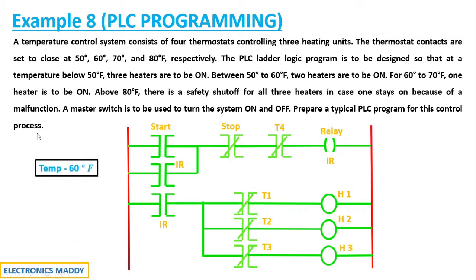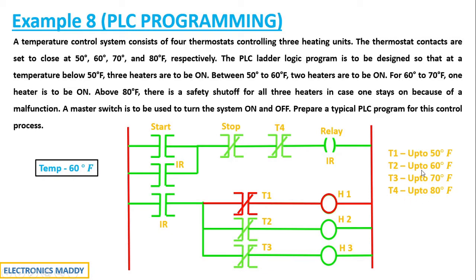Now, if the temperature is 60°F, we should have only two heaters operating. T1 will be turned off because there are only two heating units that should be on. The hierarchy shows T1 operates up to 50°F, T2 up to 60°, T3 up to 70°, and T4 up to 80°. Since T1 is now acting as an open circuit, no current flows through that path, and H1 which was previously on will be turned off.